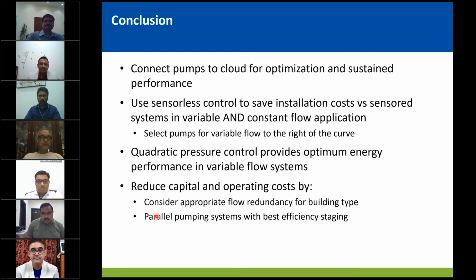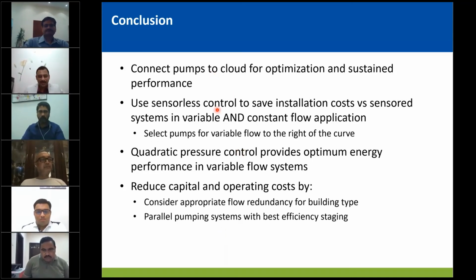And this holistic approach reduces the capital and operating cost by following all of these best practices. So consider appropriate flow redundancy, 50% or 70% split to reduce your operating costs. Consider best efficiency staging in parallel, which will save up to 34% energy savings while operating on part load conditions. With that, I pass it on to the panel for questions.